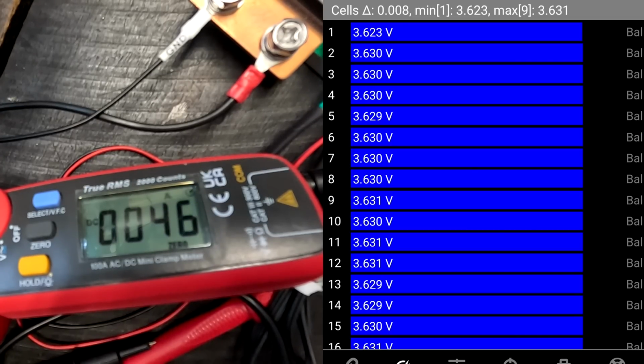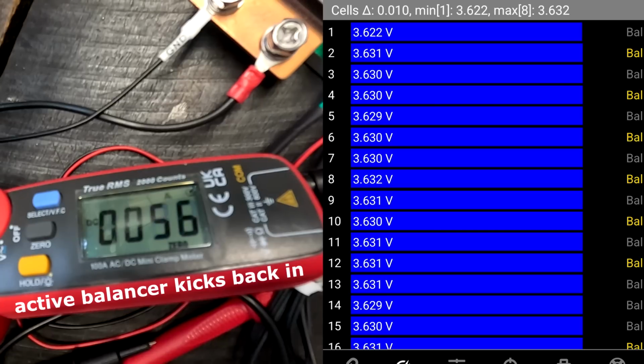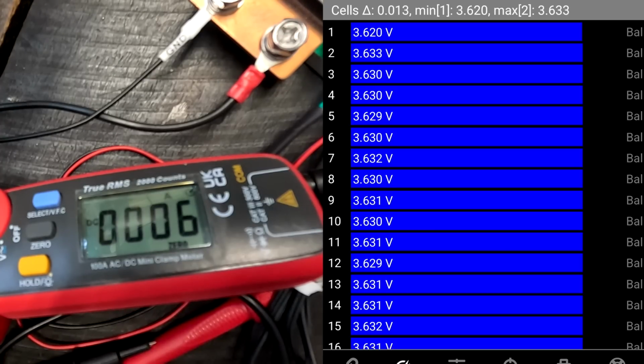So now the balancer has turned off and we are at 8 millivolts. See, it doesn't go all the way down to 5. It might be that 10 millivolt is the lowest threshold you can set. Even if we have set 5 millivolt, which is fine. You know, 10 millivolt is totally fine. So, yeah, the balancer comes back on at around 15 millivolt, and now it has turned off again, reaching 10 millivolts.